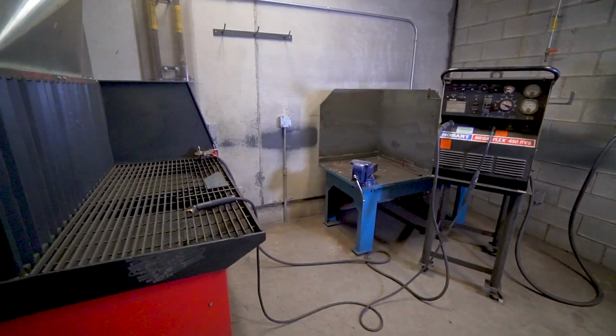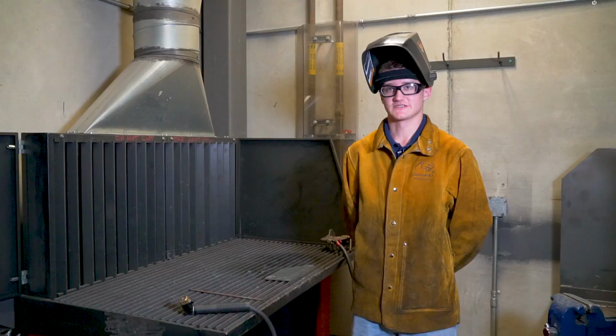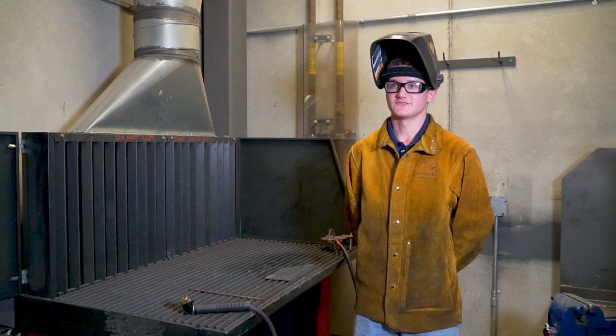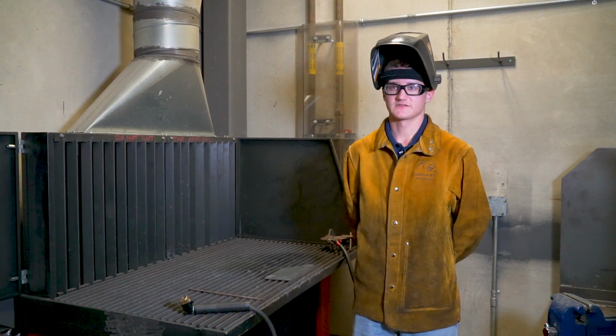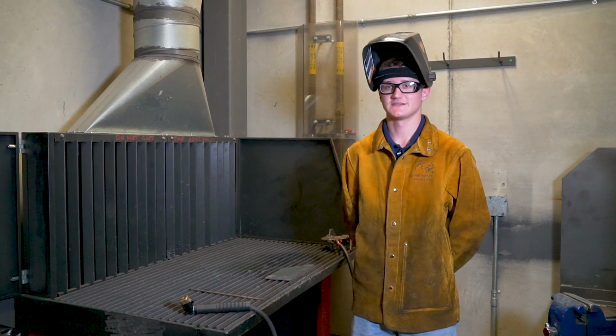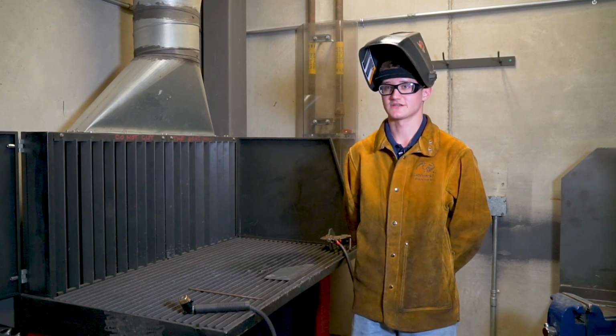The following is a demonstration of one example of a common error in welding operations that can result in stray current flowing through a building's electrical system. Stray welding currents are dangerous conditions that can occur when the secondary welding current from the power supply returns to the source through unintended means, such as the building's grounding conductors.